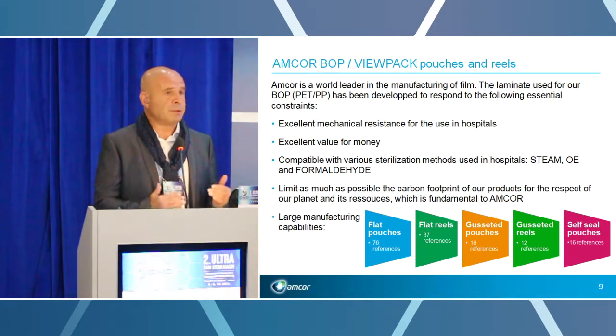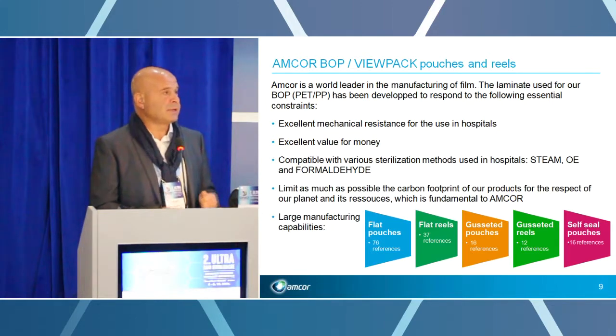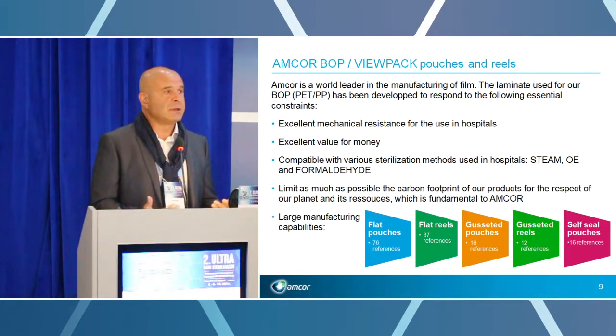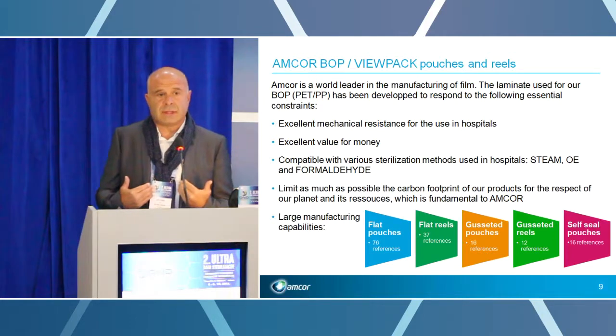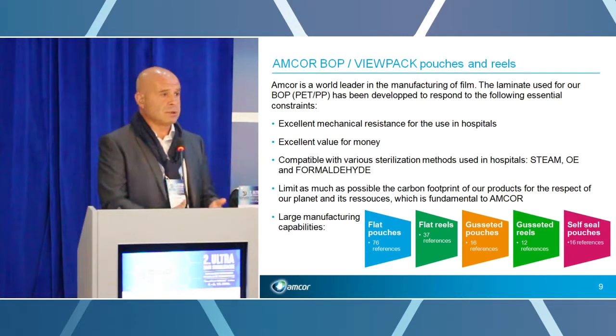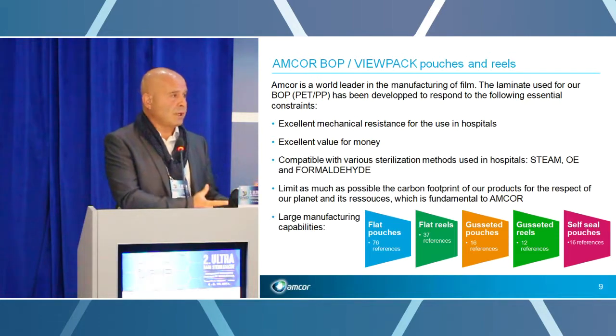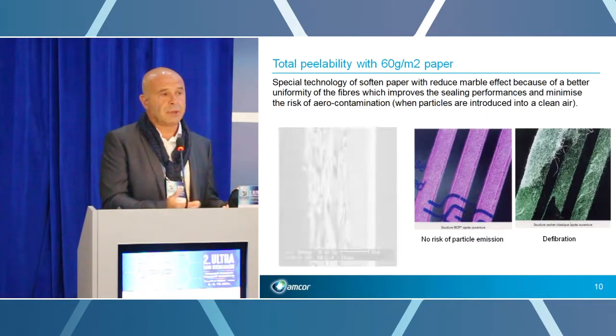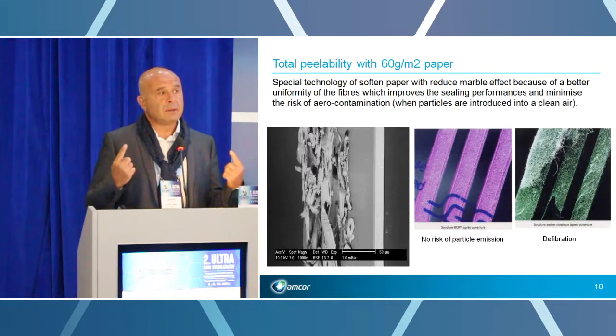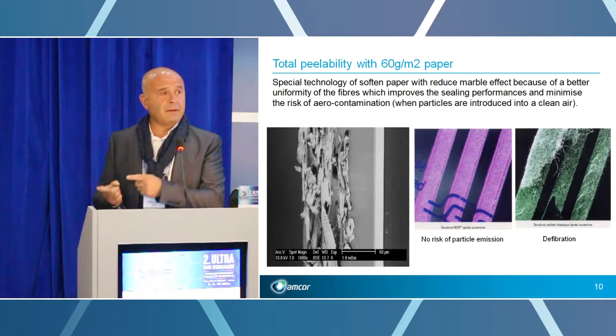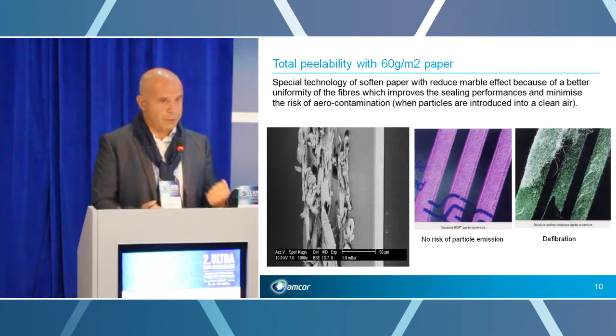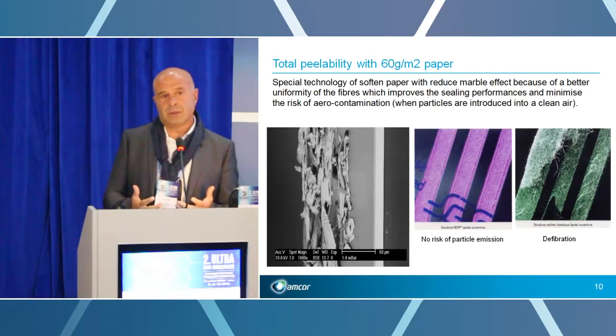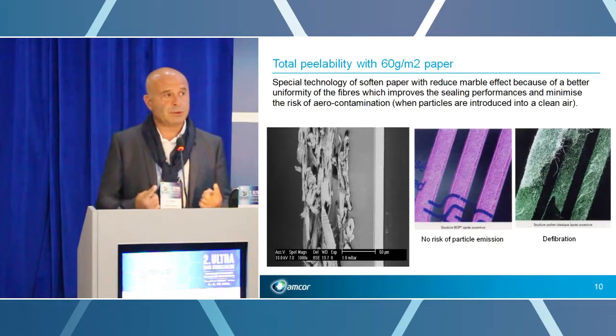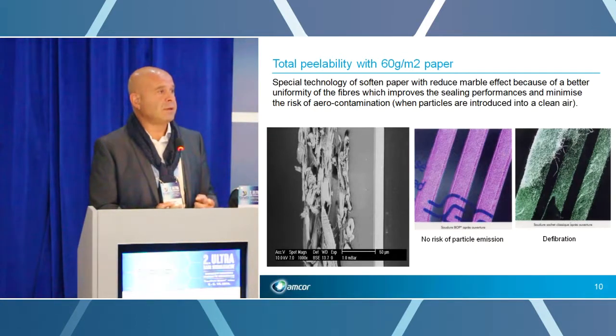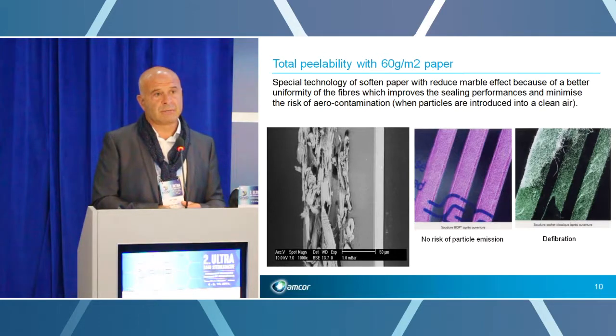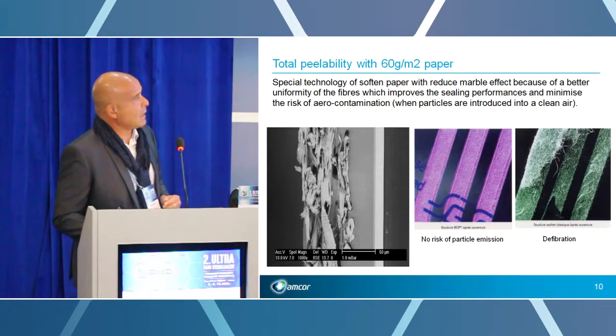When you test the packaging, it's very important that you test the peelability. In sterilization, the most important things are the closure and the sterility being okay during the sterilization cycle. But it's very important that you think about whether it's possible in the operating theater to open without any risk of contamination during the opening. It's very important that you work with the operating theater for the choice of packaging, okay?